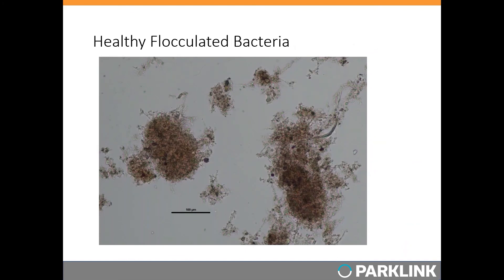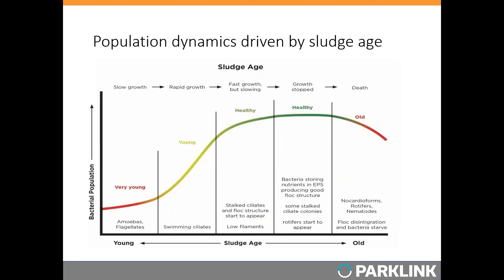Sometimes even with healthy floc you may have problems with nitrification. Mixed liquor oscillating between healthy sludge and old sludge will increasingly behave like old sludge. To review: young sludge has high soluble BOD causing heterotrophs to use nearly all oxygen; old sludge may break up or cause bulking or foaming due to filament growth, leading to oxygen limitation or poor BOD removal. In some cases, effluent ammonia levels may be higher than influent ammonia levels — this may actually be due to nitrogen limitation within the plant.